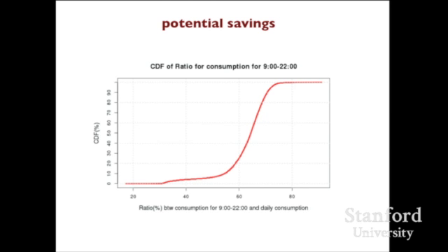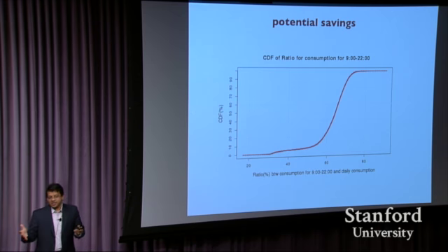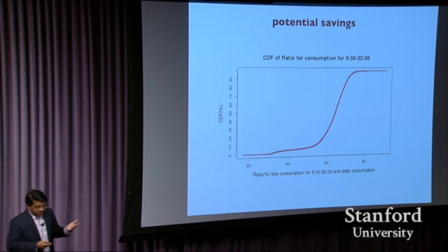If you convert this, you can actually calculate roughly what the savings would be in your bill, okay? Depending on the pricing level, if you're in the 20% pricing level, that reduction is around 25%. If you're in the 70% peak pricing level, the reduction is around 70%. So it can be huge if I could buy all my peak hour power in the off-peak. Okay. Obviously, that's kind of hard to do.